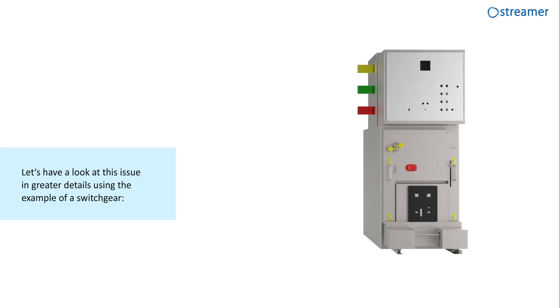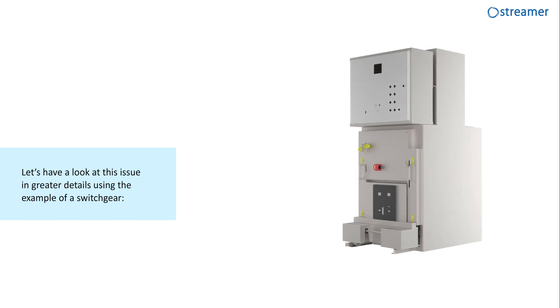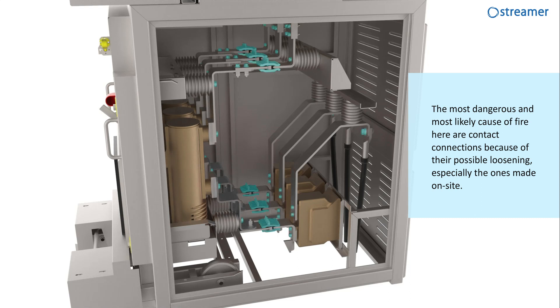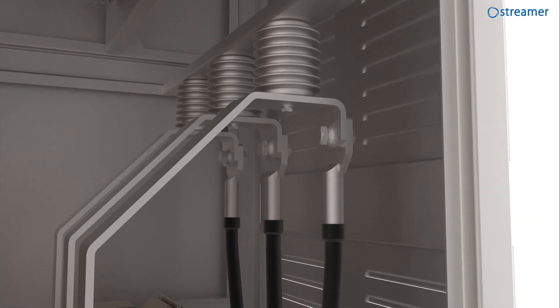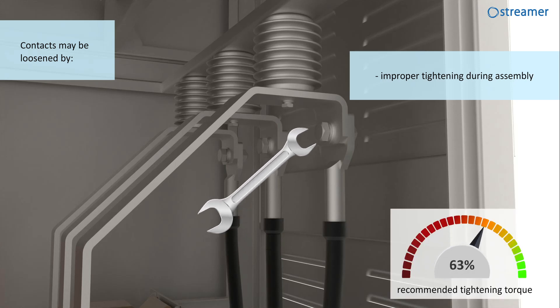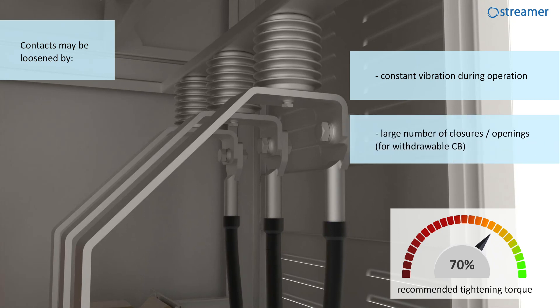Let's have a look at this issue in greater detail using the example of a switchgear. The most dangerous and most likely cause of fire here, as with any MV or LV equipment, are contact connections because of their possible loosening, especially the ones made on site. Contacts may be loosened by improper tightening during assembly, constant vibration during operation, or a large number of closures, openings, for withdrawable circuit breakers.